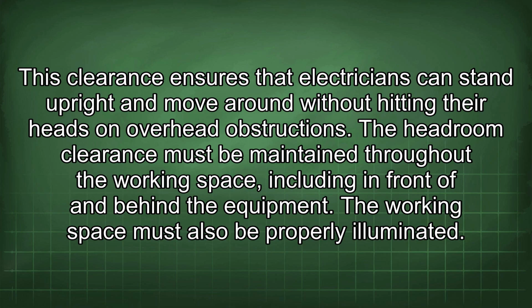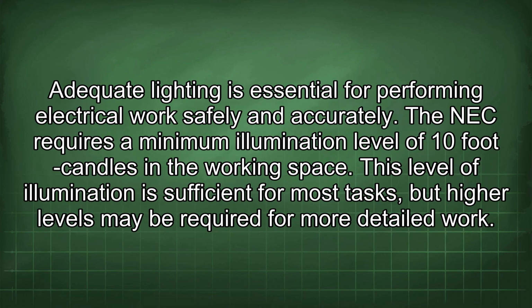The working space must also be properly illuminated. Adequate lighting is essential for performing electrical work safely and accurately. The NEC requires a minimum illumination level of 10-foot candles in the working space. This level of illumination is sufficient for most tasks, but higher levels may be required for more detailed work.